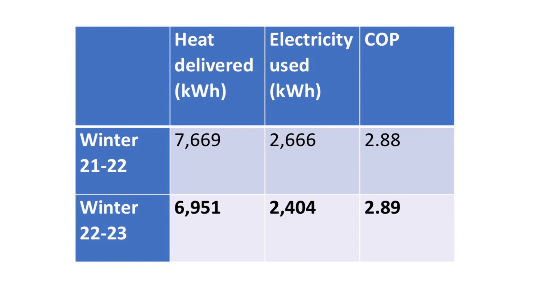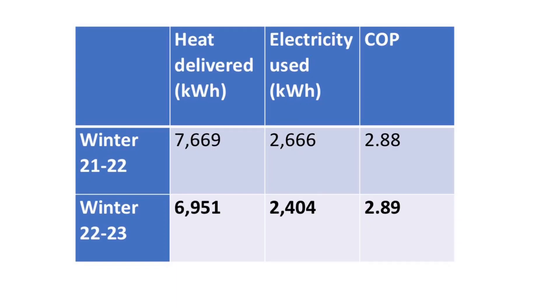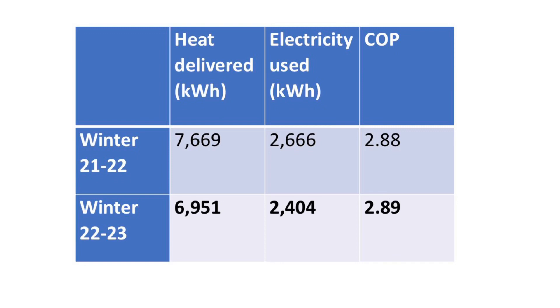What about this year? Well, the heat pump delivered a little bit less heat — 718 kilowatt hours less over the same time period — at 6,951 kilowatt hours in total. To do this it used 262 kilowatt hours less electricity, at 2,404 kilowatt hours total for the winter. So this year we had an efficiency of 289.1%, or a COP of 2.89.